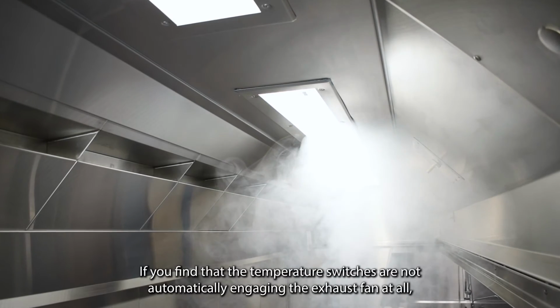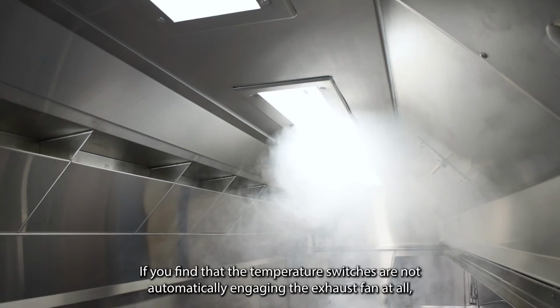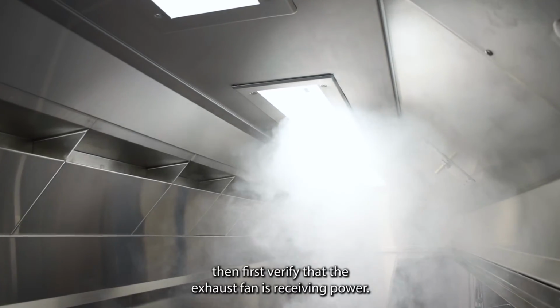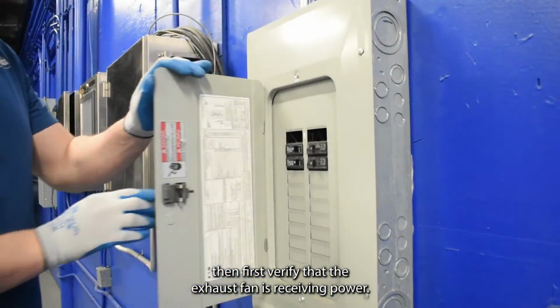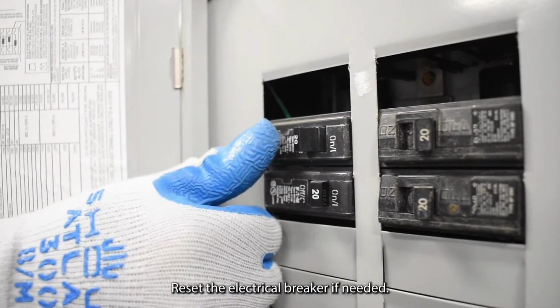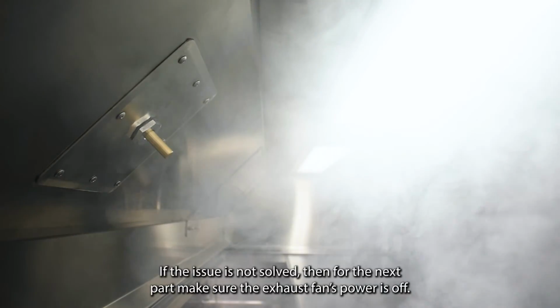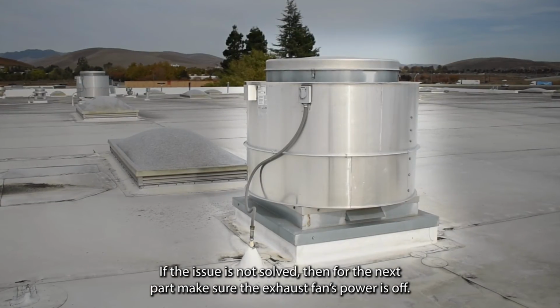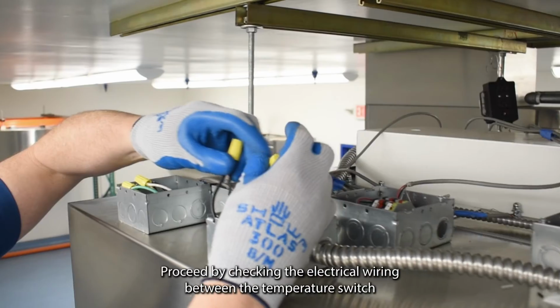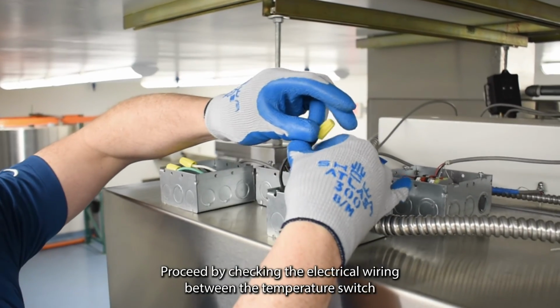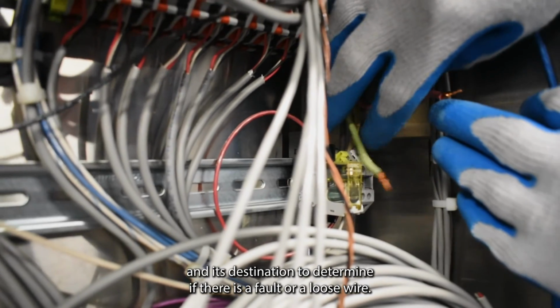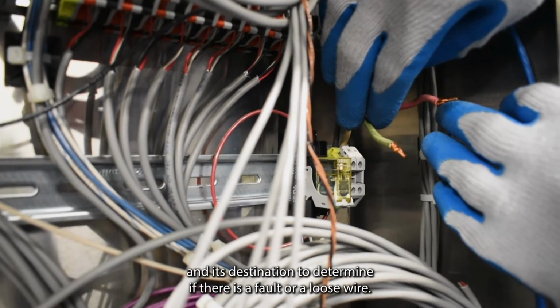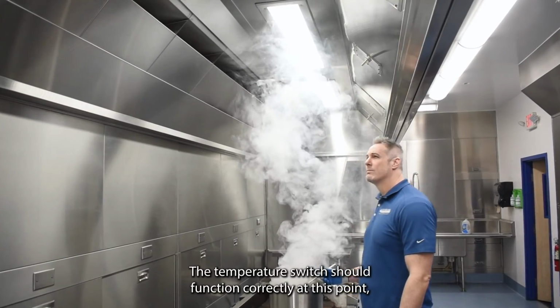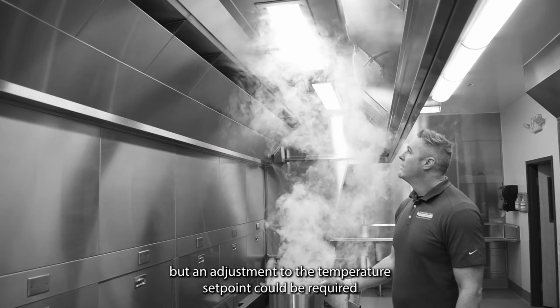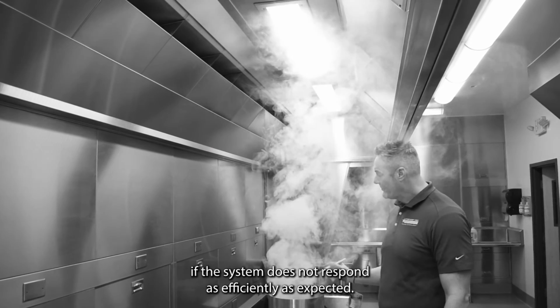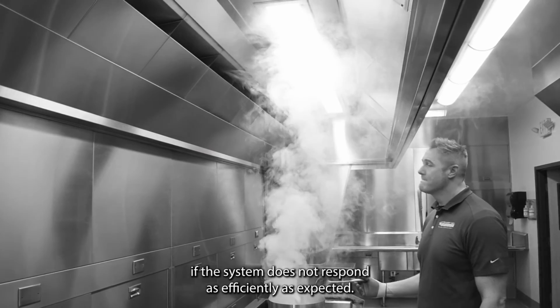If you find that the temperature switches are not automatically engaging the exhaust fan at all, then first verify that the exhaust fan is receiving power. Reset the electrical breaker if needed. If the issue is not solved, then for the next part make sure the exhaust fan's power is off. Proceed by checking the electrical wiring between the temperature switch and its destination to determine if there is a fault or a loose wire. The temperature switch should function correctly at this point, but an adjustment to the temperature set point could be required if the system does not respond as efficiently as expected.